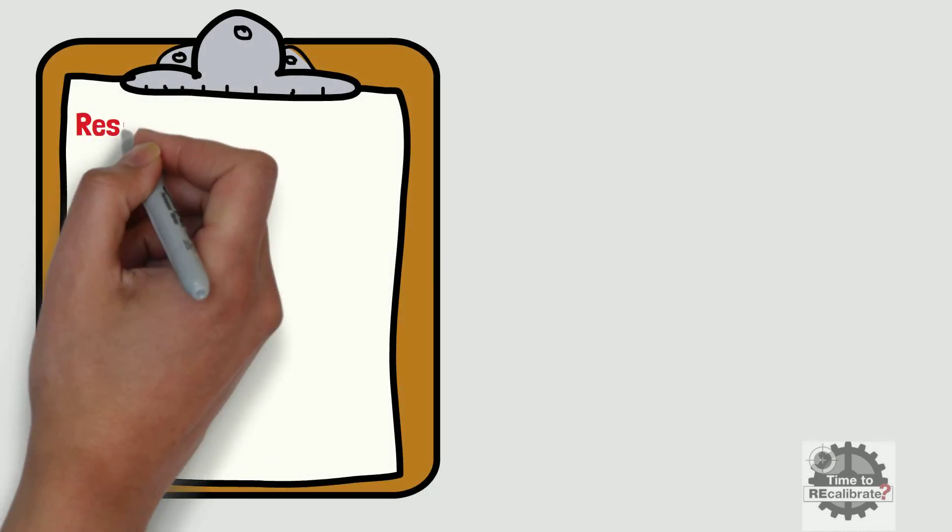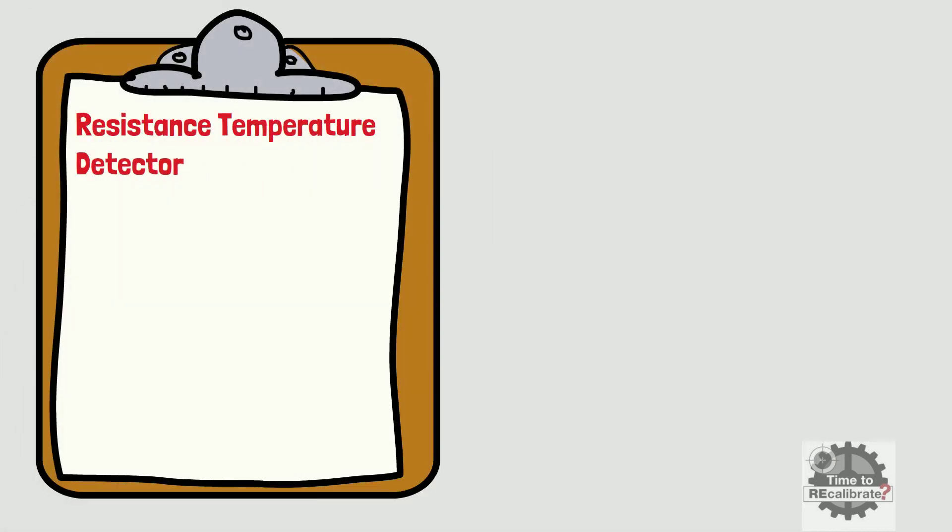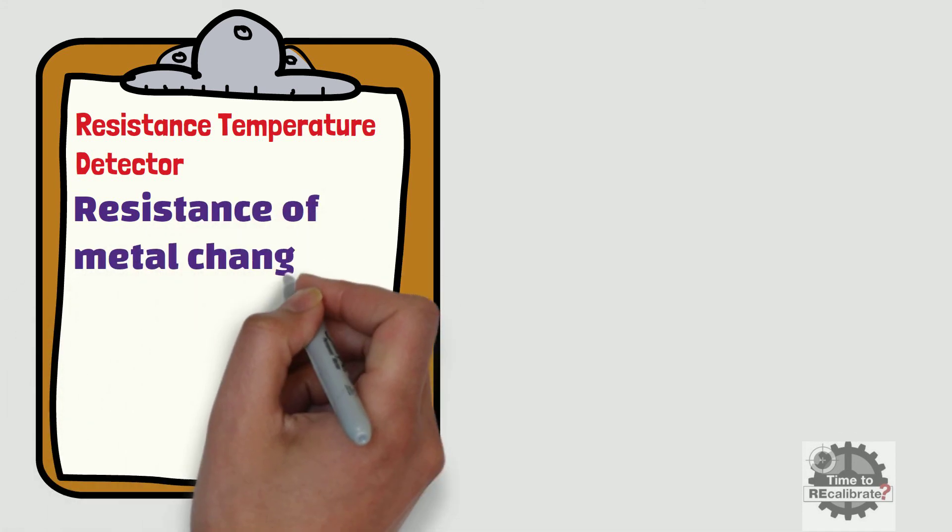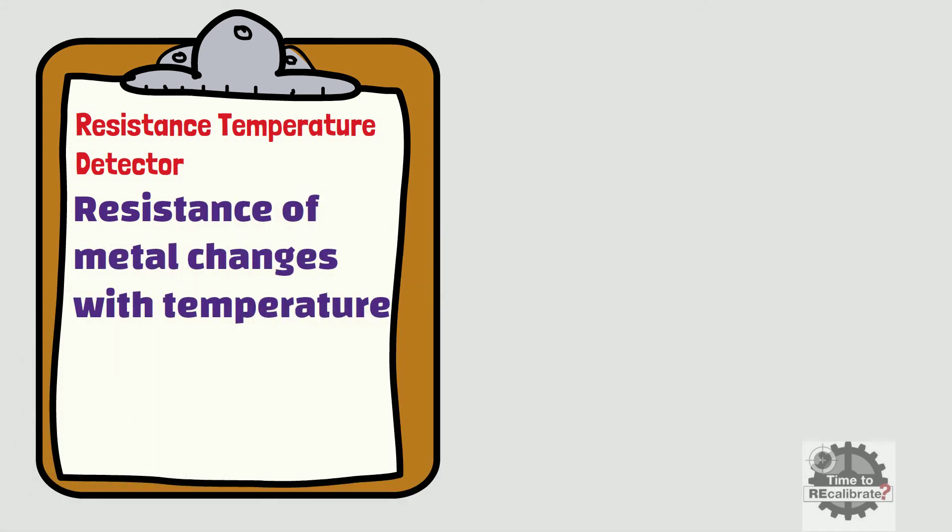The second type is resistance temperature detector. It is a temperature sensor which measures temperature using the principle that the resistance of metal changes with temperature. In other words, electrical resistance of certain metals increases and decreases in a predictable manner as temperature changes. This means RTD has a positive temperature coefficient.